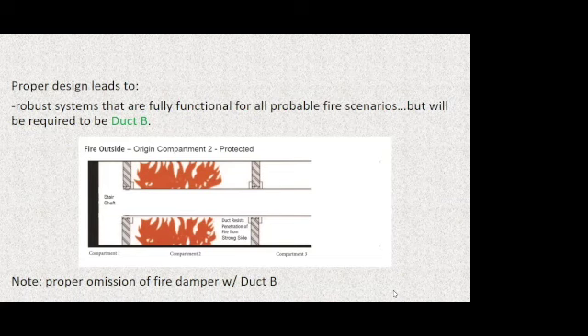And one of the dirty little secrets of the fire-rated duct industry is that most products have not been tested completely. It is one of the rare test standards where the test laboratories will allow what they call provisional listings. We'll see what a provisional listing means and the dangers of not vetting which test specimens were tested when we are applying designs that are based on provisional testing. Because when we take that damper out, which we want to, we don't just want to, the code demands that we take that damper out if it's going to interfere with our smoke control system. When we take it out, we need to ensure that we're providing equivalent protection to the compartments where we're not providing the opening protective. And that means considering that specific design scenario that comes first to mind when we're needing to get that air safely to the stair shaft.